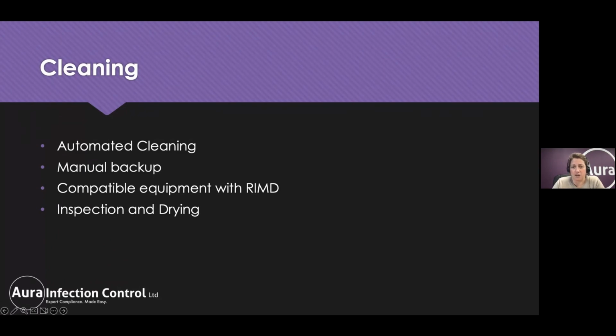Cleaning is a subjective term, so it's not always easy to measure. And clean isn't a scientifically defined term either. It's a relative concept. So we are going to clean our items so that they are visibly clean to our inspection under an inspection lamp, and we're going to use things like residual protein tests to make sure they are clean and void of protein. We know that retained soil on the surface of an instrument will inhibit the disinfection and sterilization stages, so we need to make sure that this stage is completed effectively.